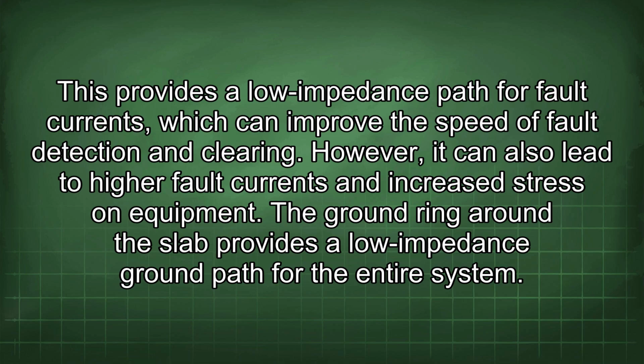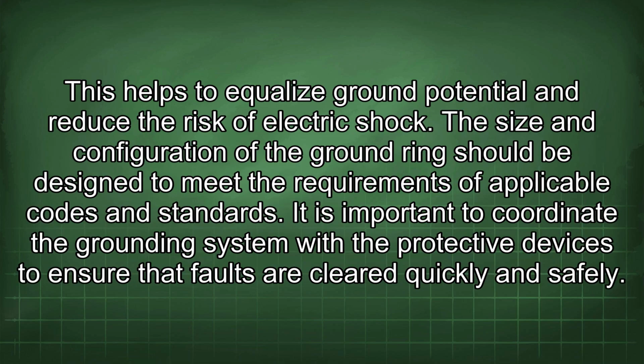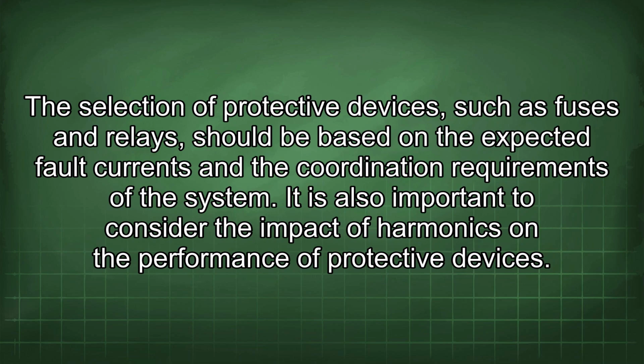The ground ring around the slab provides a low-impedance ground path for the entire system. This helps to equalize ground potential and reduce the risk of electric shock. The size and configuration of the ground ring should be designed to meet the requirements of applicable codes and standards. It is important to coordinate the grounding system with the protective devices to ensure that faults are cleared quickly and safely. The selection of protective devices, such as fuses and relays, should be based on the expected fault currents and the coordination requirements of the system.